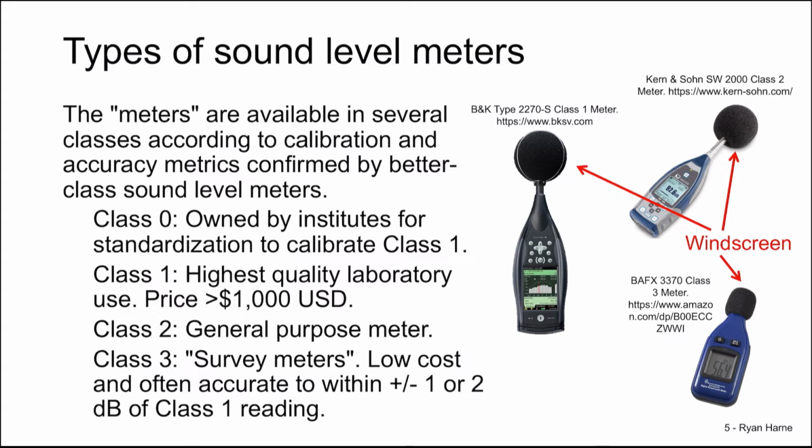Finally, we see a black foam piece at the ends of all of the microphones here for the sound level meters. These are called wind screens. They are in place to minimize the acoustic turbulence created when wind flows over the surface of the microphone.